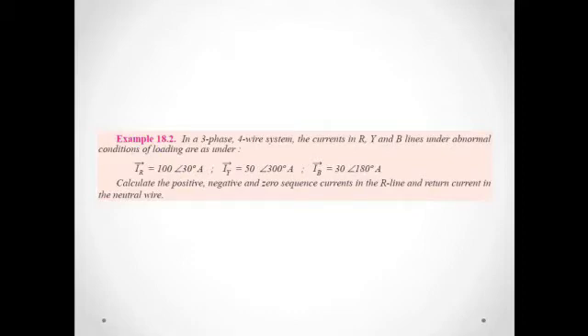This is our first example. We have a three-phase four-wire system. The current in the red, yellow, and blue lines under abnormal conditions are: IR = 100 at 30°, IY = 50 at 300°, and IB = 30 at 180°. We have to calculate the positive, negative, and zero sequence currents in the red line, and then the return current in the neutral wire.